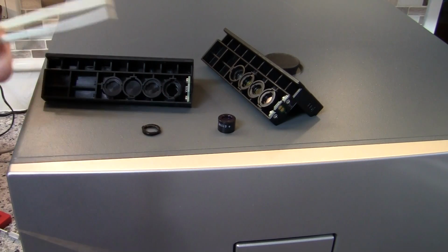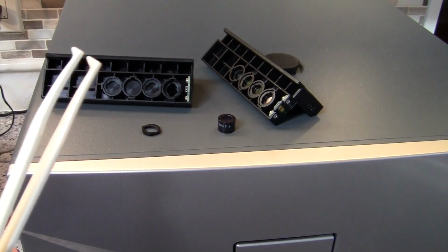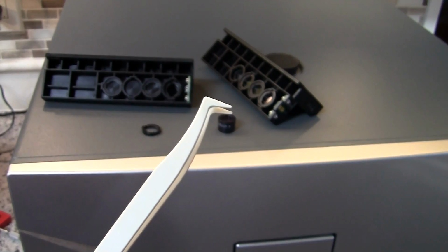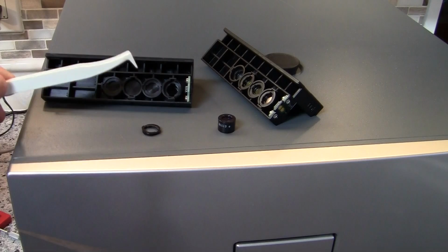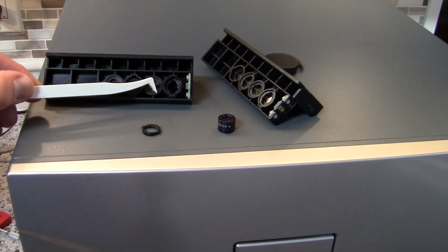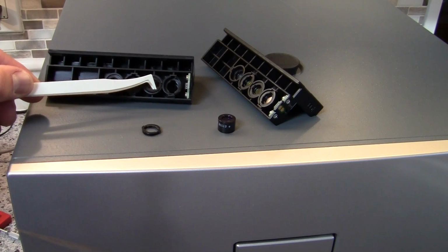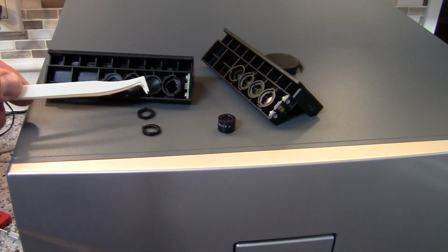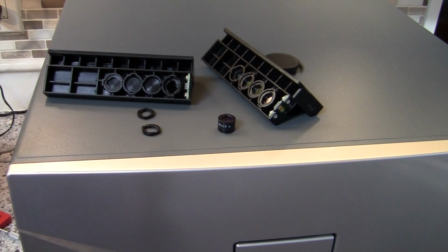The instrument comes with a couple of different tools for managing filters. I find that these tweezers work best, and in order to get the filter O-rings off, you simply run one of the pointed ends of the tweezers underneath the O-ring and then it will lift out. You can also use the tweezers for replacing the O-rings. Here's how that works.